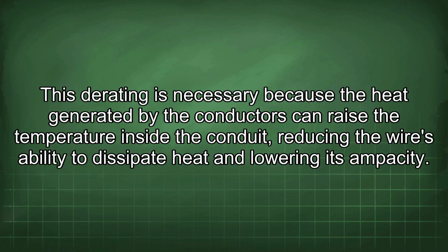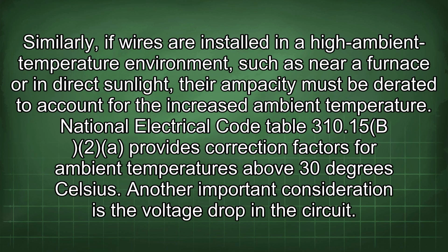310.15(B)(3). This derating is necessary because the heat generated by the conductors can raise the temperature inside the conduit, reducing the wire's ability to dissipate heat and lowering its ampacity. Similarly, if wires are installed in a high ambient temperature environment, such as near a furnace or in direct sunlight, their ampacity must be derated to account for the increased ambient temperature. National Electrical Code Table 310.15(B)(2)(a) provides correction factors for ambient temperatures above 30 degrees Celsius.